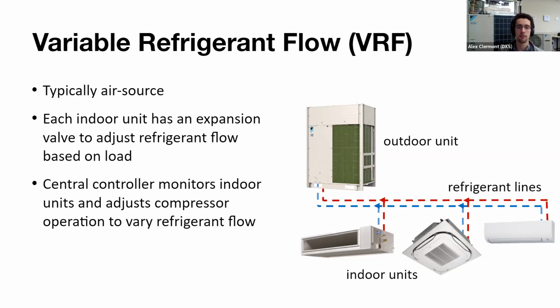Now, there are actually two different kinds of VRF. There's VRF heat pump and VRF heat recovery. Heat pump systems are also called switchover systems, and heat recovery is sometimes called simultaneous system. What we're looking at here is a VRF heat pump system, and the entire system has to be in either heating or cooling. Now, let's say the entire system is in heating. Each zone can modulate how much refrigerant it wants for its own zone, but it cannot go into cooling. It has to be in heating.